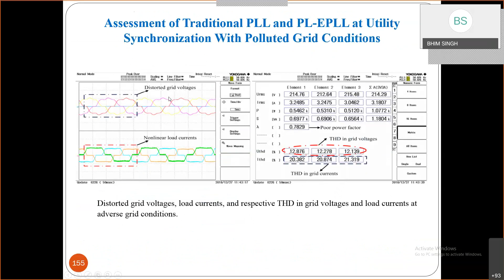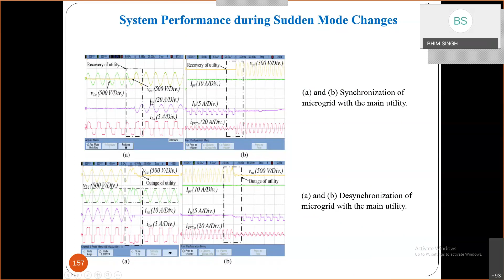When we feed the non-linear load, the voltage was distorted, but when we switch on this system, the voltage profile is also improved, without much problem. We are able to synchronize again to the grid after it reappears, in about 3/4 cycle, without much problem. When the system is off you can see the voltage distortion due to non-linear load; when our system is on, the voltage profile improves and the grid current becomes sinusoidal.